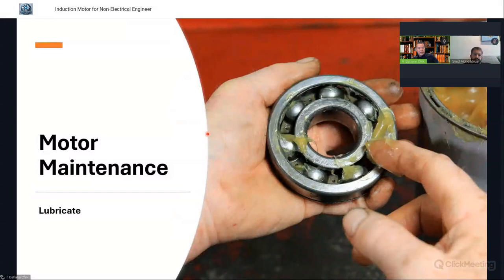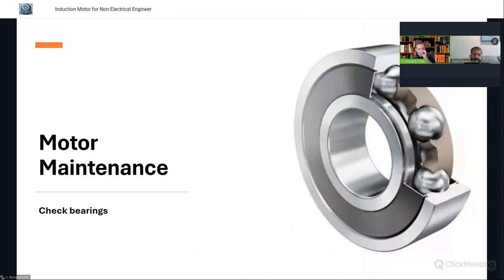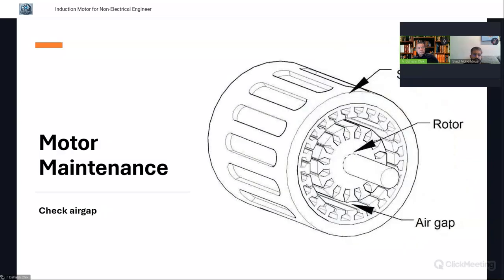In terms of motor maintenance, you need to lubricate the bearing, and also check the bearing free play, and also the air gap that I discussed just now. If there is a runaway in terms of air gap, that is indicative that the bearing has some failures. It may give way, and then the rotor may rub the stator core, so it causes more problems. So for the maintenance guy, you need to ensure that the bearings are checked regularly. So this is what I'm talking about on the air gap. It should be measured.